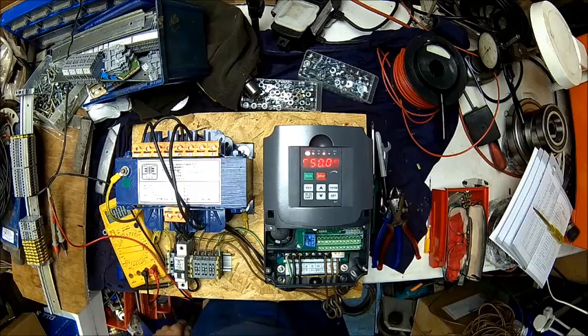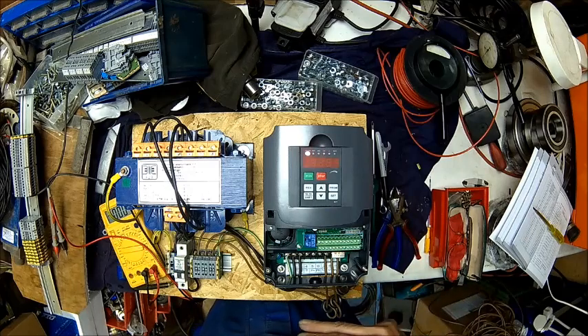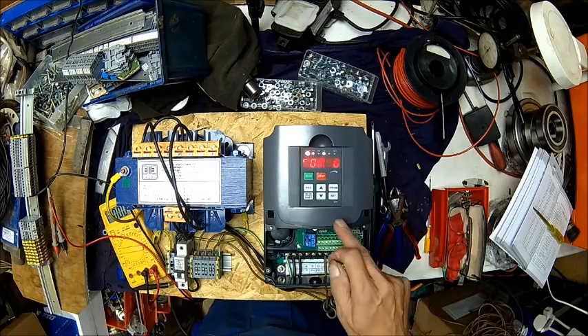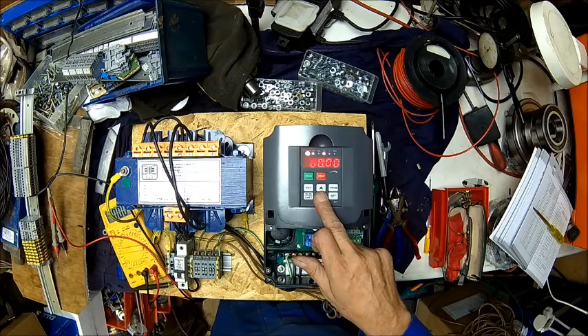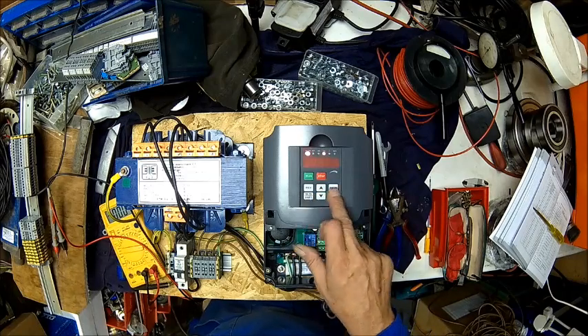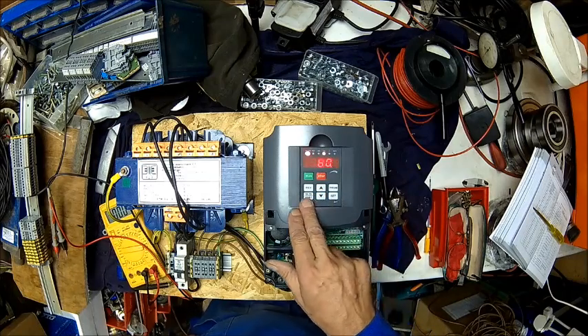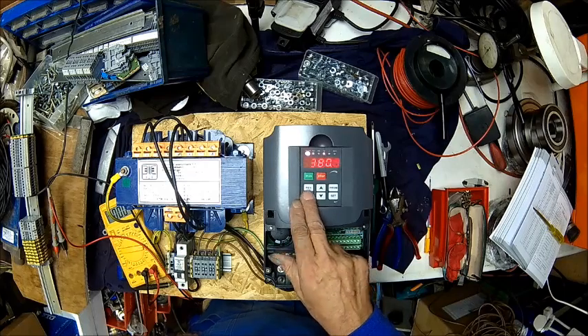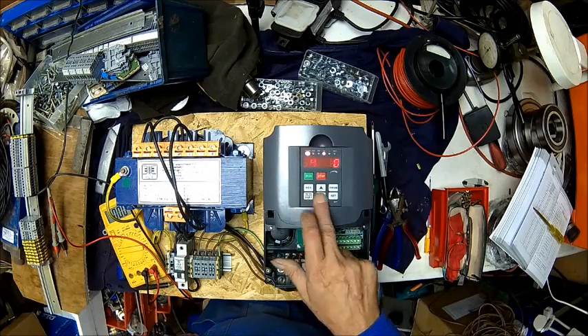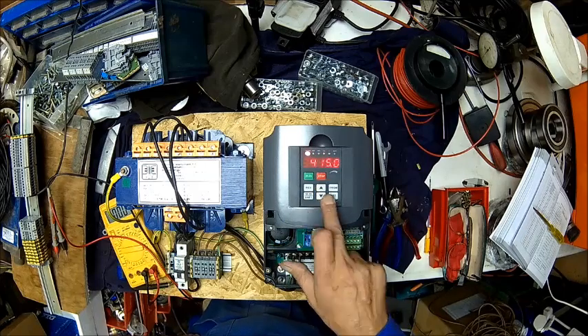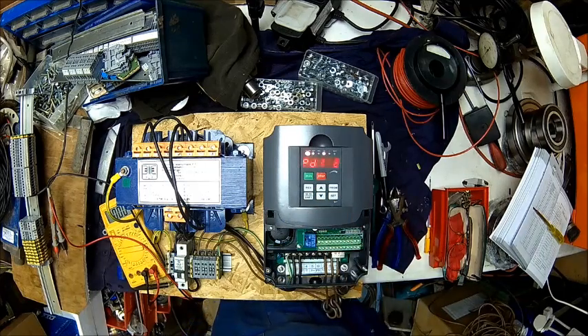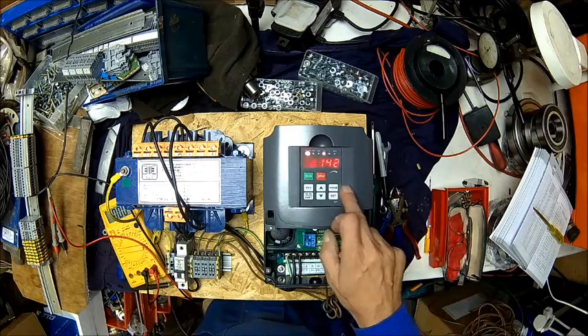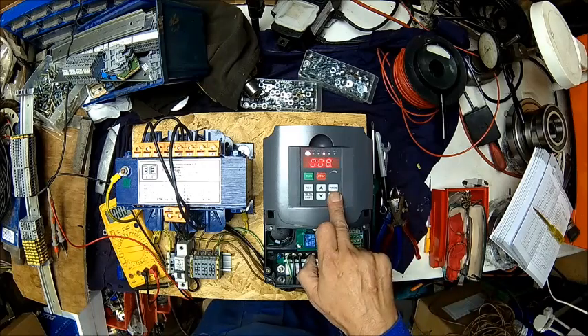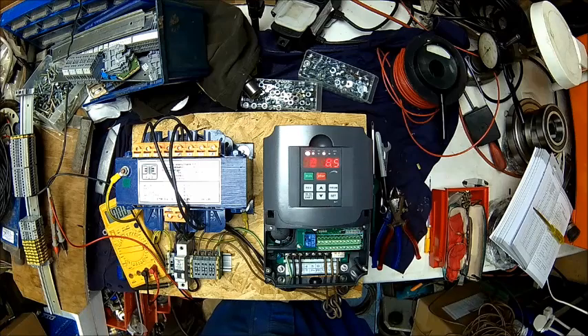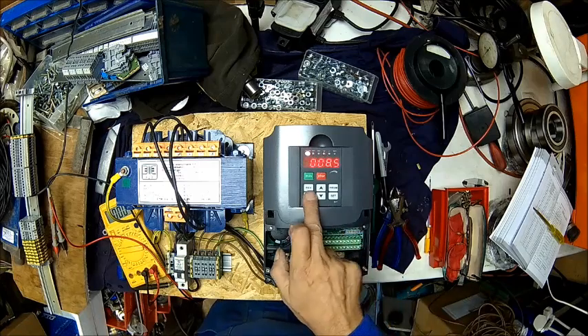So what we also need to check is our motor ratings. Even if we don't have a motor, we need to tell this thing what our maximum ratings are. So that's parameter 141. This is 400 volts, or 415 in our case. 415. Set. And our maximum current, which is 142. It's set to 8.5. The inverter can actually do 9, so I would set that to 9.